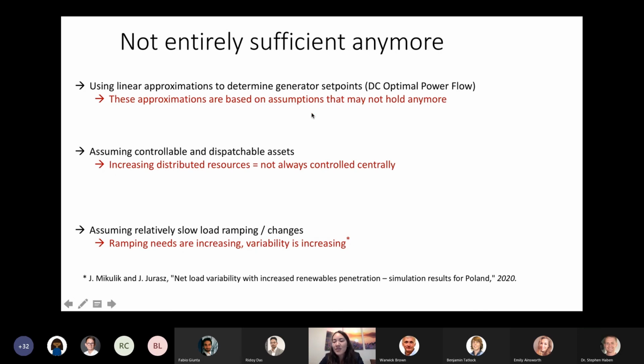So why can't we use these old approaches anymore? That's the point of this talk. A lot of the approximations that worked decently well in practice from the 80s through the 2010s are based on assumptions that might not hold anymore. The DC optimal power flow, if you're familiar with it, assumes the lines are lossless, that all voltage magnitudes are the same, that phase angle differences between neighboring nodes are small, and that there's no reactive power modeling.